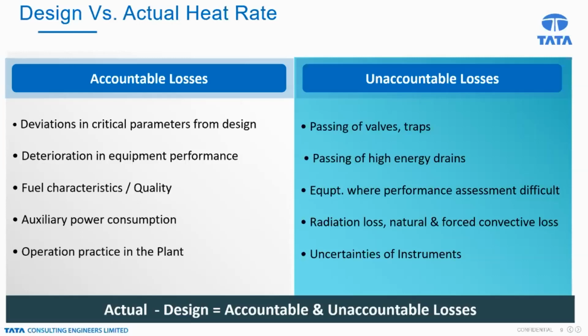So these are all the categories which come under the accountable losses. And we have several factors which we cannot measure or account for, because of passing of valves and steam traps, passing of high energy drains, for example, heated drains going into the condenser, which is a typical thing. We will lose heat rate because of that. And equipment assessment is very difficult, and of course, radiation loss, natural and forced convective loss, and uncertainties in the instrument. So these are all unaccountable losses.